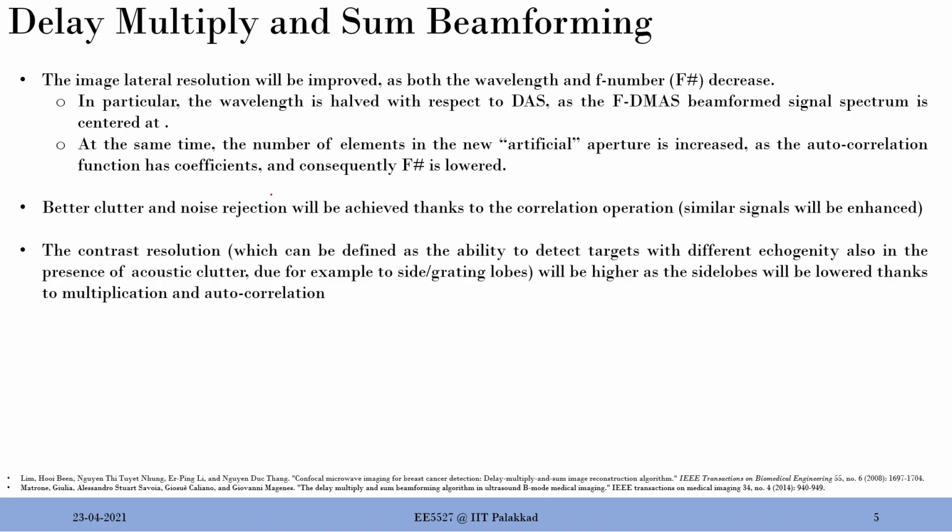At the same time, contrast resolution is nothing but the ability to distinguish between two intensity levels in the image. If two regions of the image are closer in intensity, then we won't be able to distinguish between them, right? But the moment they get separated slightly in intensity, you may be able to distinguish between them. So that contrast resolution is much better in the case of delay, multiply, and sum, as you will notice in the images.